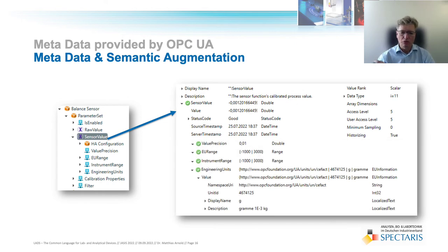However, more metadata is available. For example, the expected range of the value, the value's use range as well as its absolute range, and, for example, its engineering unit, adhering to a United Nations standard. Bottom line, when looking at a single process value, OPC UA provides by default a lot of metadata.